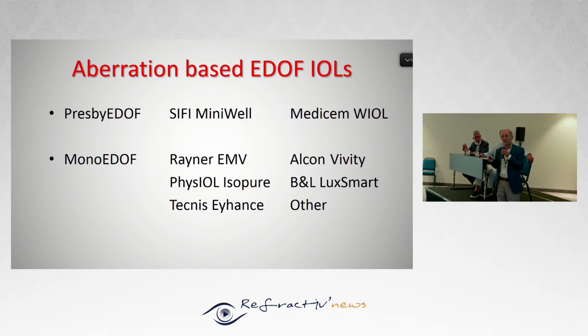The SIFI Miniwell has a positive spherical aberration in the center surrounded by a negative spherical aberration annulus. The Medicem has a big positive spherical aberration through all the lens surface. This is probably too much.